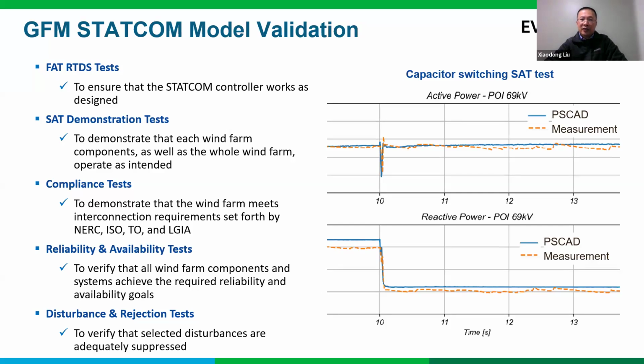If there are differences between recorded data and simulation, investigations would be performed. On the right, I just show you an example of a PSCAD simulation and measurement comparison on a capacitor switching event. The wind farm and the STATCOM response closely match the measurement. So this kind of simulation helps us to gain confidence in the PSCAD model.